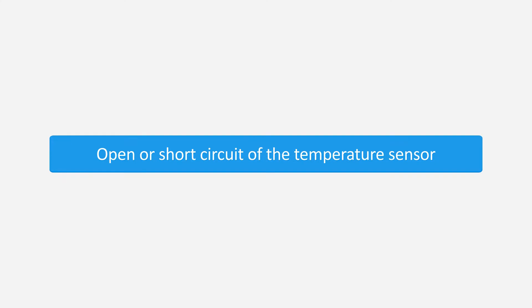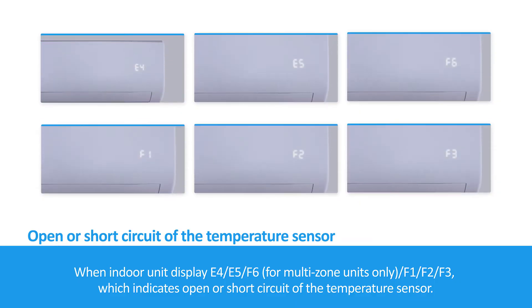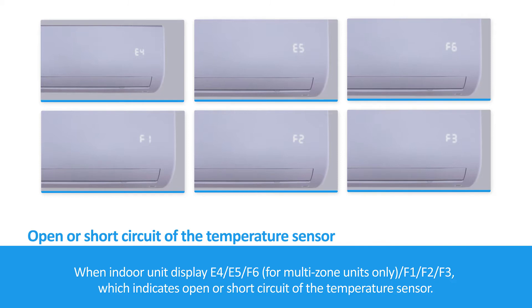Open or short circuits of the temperature sensor. When the indoor unit displays E4, E5, F6 (for multi-zone units only), F1, F2, or F3, this indicates open or short circuits of the temperature sensor.